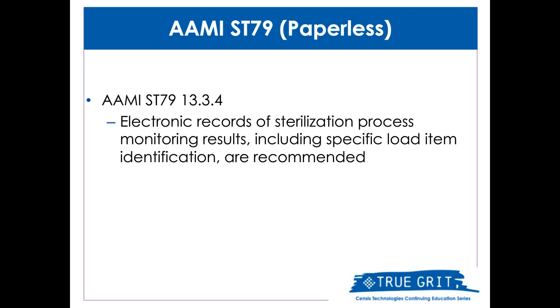Looking at ST79 recommendations for steam sterilization, AAMI is consistent with recommendations on electronic record keeping for sterilization, monitoring, and load identification. Again, this is regardless of the method of reprocessing.